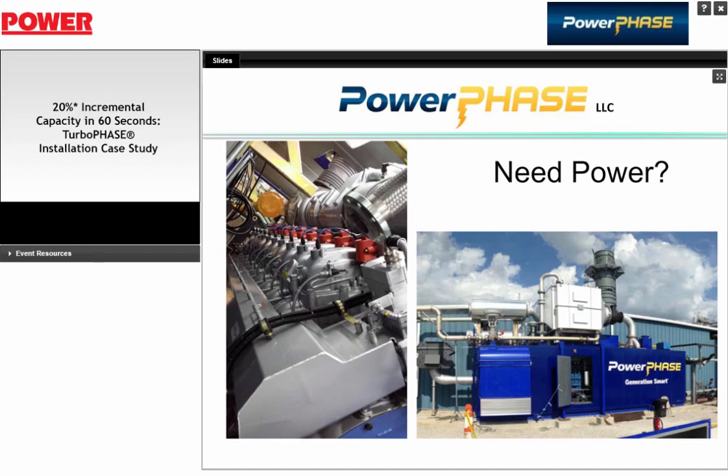literally dozens of customers go to the OEMs, and when I say the OEMs, every one of the large OEMs that make gas turbines, and ask them anywhere from guys that have long-term service agreements to guys that just buy on a parts basis, on a transactional basis, ask the OEMs that question, and we're still moving forward with all those customers. So I think we're getting a very favorable response, and part of the reason is because the OEMs advertise that all of their gas turbines are designed for 5% injection. And Siemens Westinghouse would actually have a bigger number than that. And if you have an older frame machine, there's publications from General Electric that are all up to 9% injection.